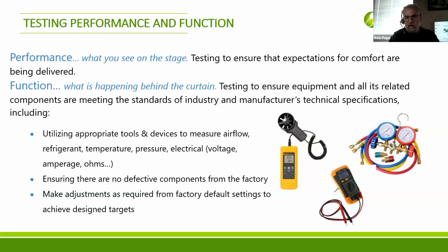That's basically, is the air being delivered through a ducting system that is sized adequately, that it doesn't squeeze and pressurize the air and restrict its flow. That's a pressure. We're also, if we have a dual fuel system, going to want to measure the gas pressure, the inlet pressure on the furnace. And we want electrical measuring equipment to see if we're drawing the right amount of amps from the compressor, for example, a motor. We have enough, the right amperage, ohms, and voltage going everywhere it needs to go.